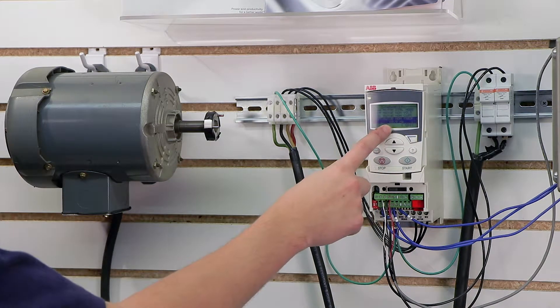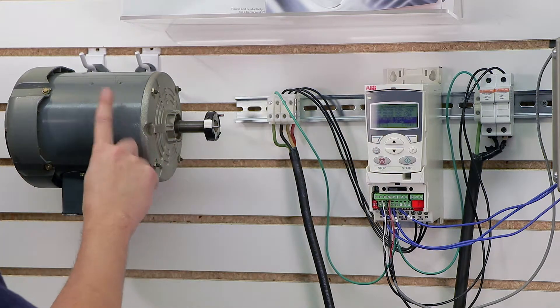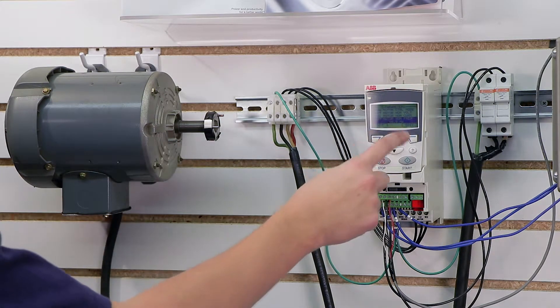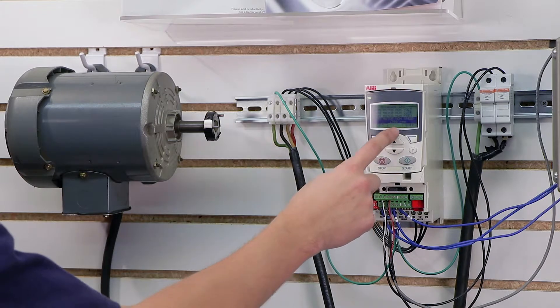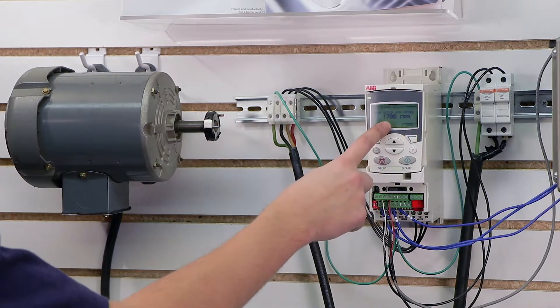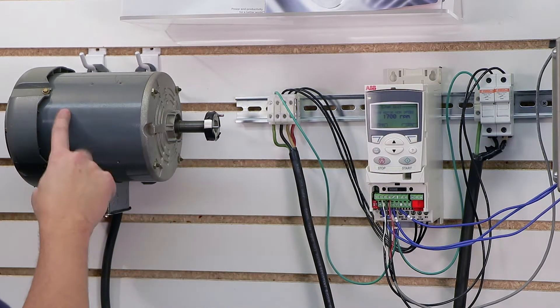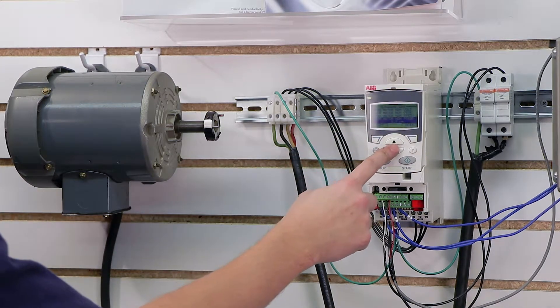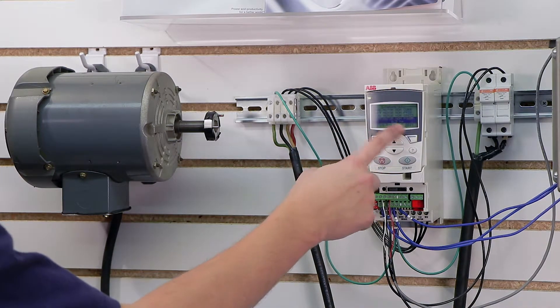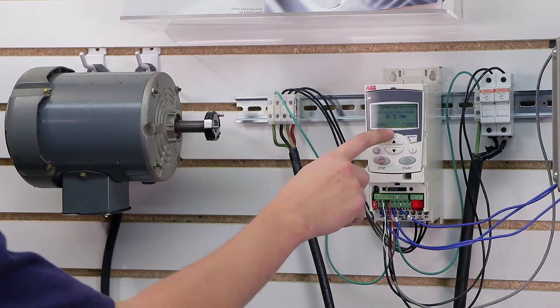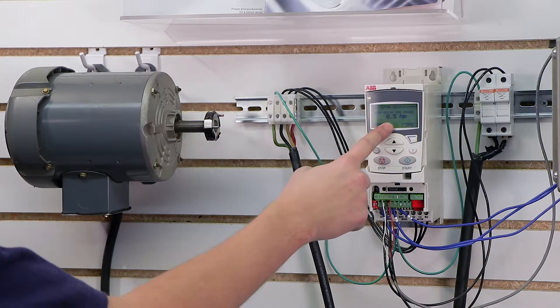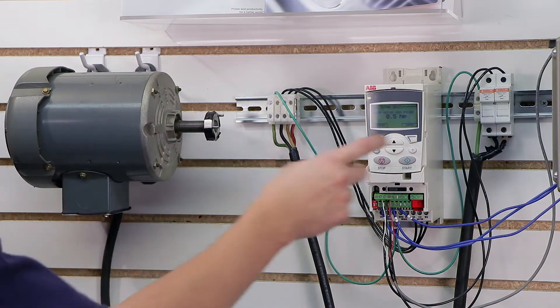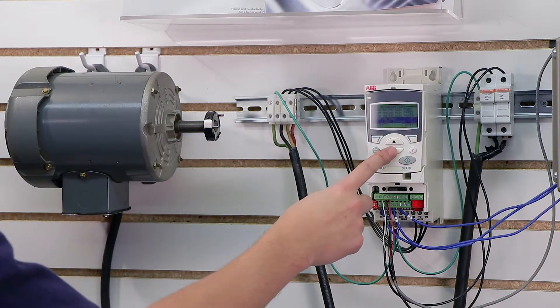Motor nominal frequency is my nameplate frequency - my nameplate frequency is 60 hertz, so I'm going to leave mine at the default 60 hertz. Motor nominal speed is my RPM rating on my nameplate of my motor - mine's 1700, so I set that accordingly and click save. And my motor nominal power is the actual horsepower rating of my motor - in this case I set it to a half horsepower, which also matches the nameplate information.